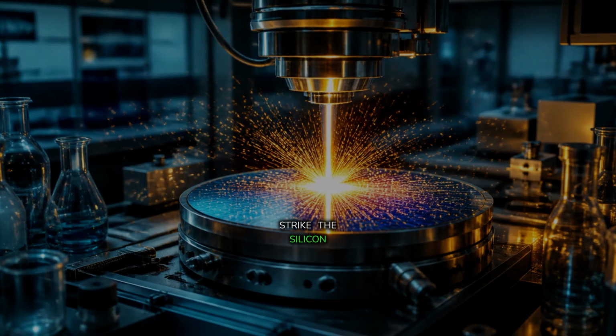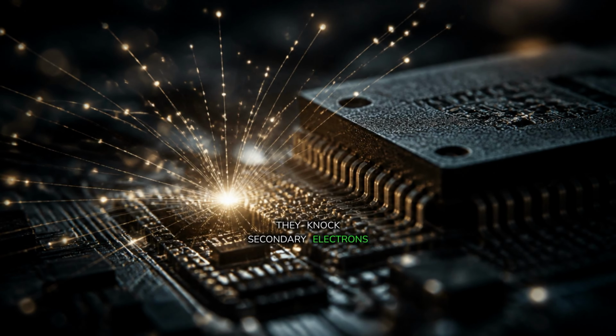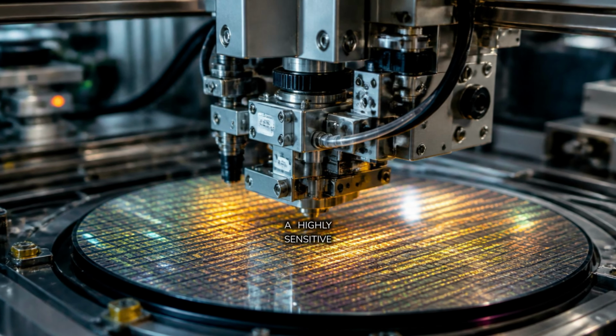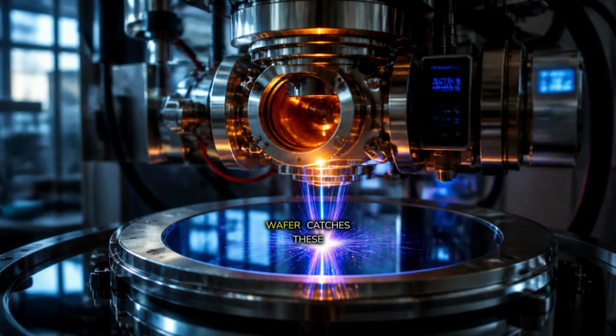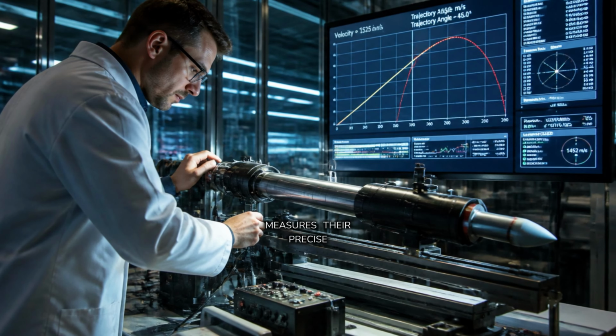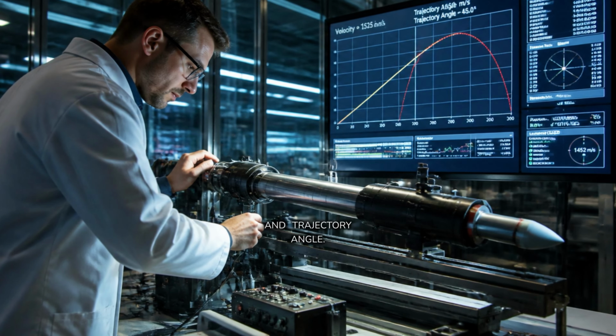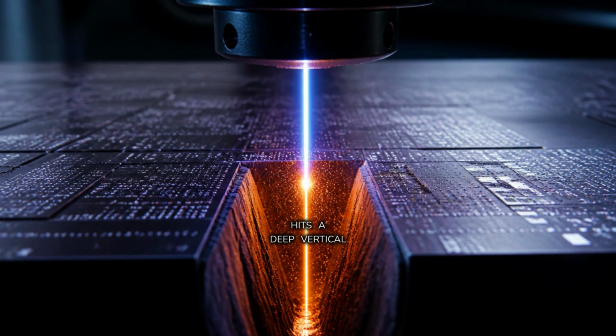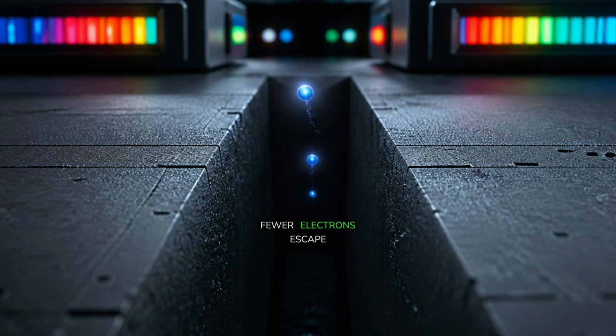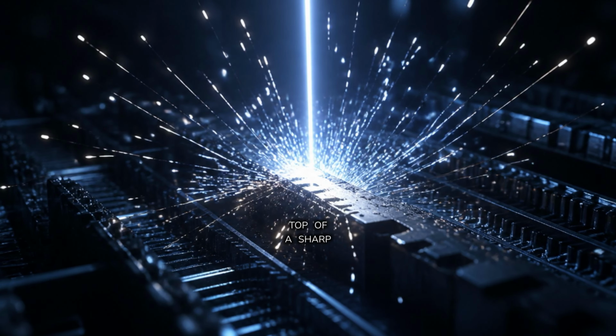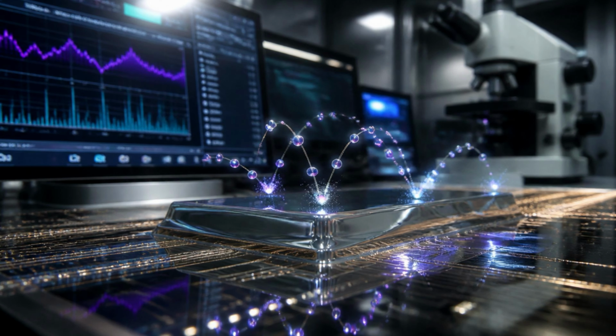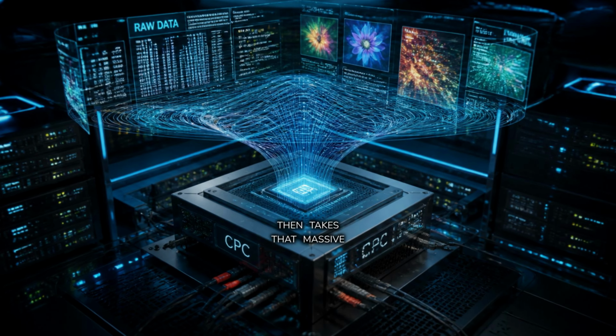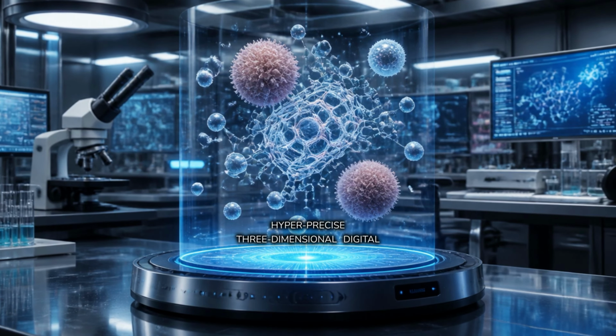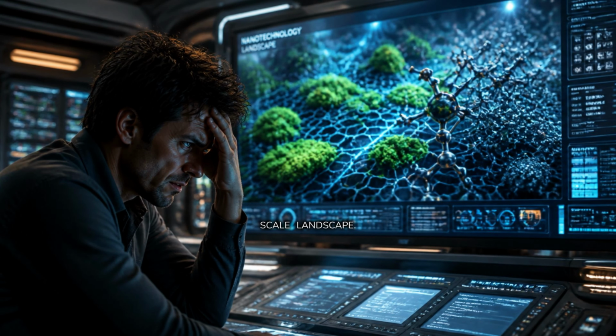As these electrons strike the silicon structure, they knock secondary electrons out of the atoms on the chip's surface. A highly sensitive detector positioned above the wafer catches these escaping secondary electrons and measures their precise quantity, velocity, and trajectory angle. If the electron beam hits a deep vertical trench, fewer electrons escape back to the detector. If it hits the top of a sharp transistor ridge, a flood of electrons bounces back cleanly. The machine's software then takes that massive stream of raw data and reconstructs a hyper-precise, three-dimensional digital image of the nanometer scale landscape. But even this creates a massive QA crisis.